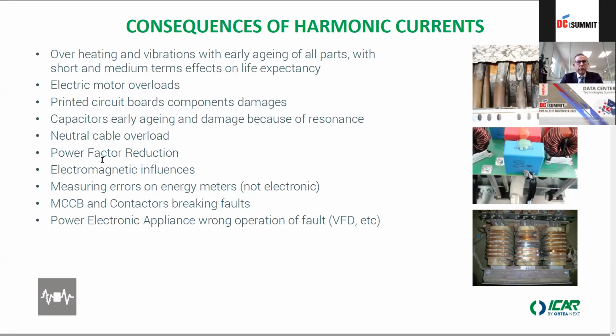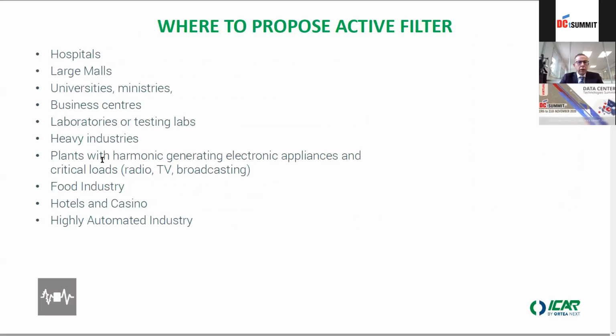When you have a power factor of 0.7 due to harmonics on the lines, you will be obliged to absorb, or be able to absorb, only 700 kVA instead of the complete 1000 kVA. So these are some of the troubles caused by the harmonics. So when is a harmonic filter needed? An active filter is needed when you have high-end user level.